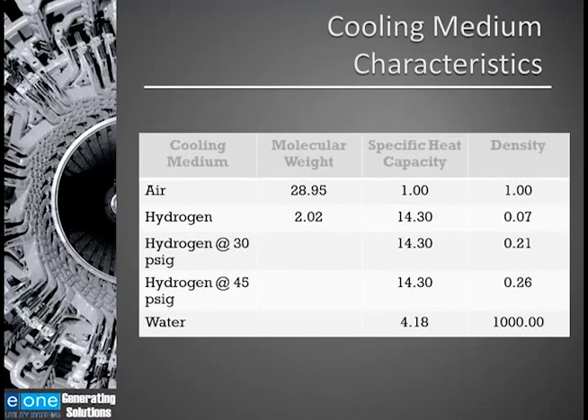This chart supports the density and specific heat transfer characteristics discussed in the previous slide. Again, hydrogen at 45 psig is 4 times less dense than air and has a specific heat capacity 14 times greater than air. Again, meaning that you can spin the generator a lot easier and you're much more effective in removing heat from components using hydrogen versus air.